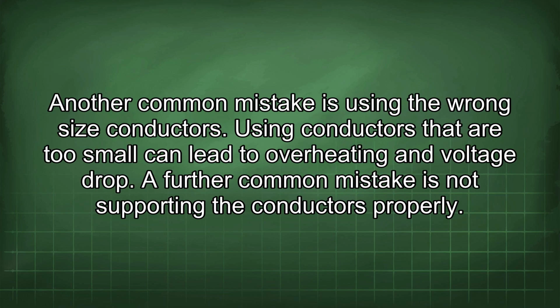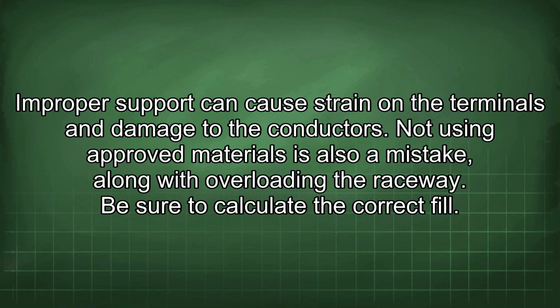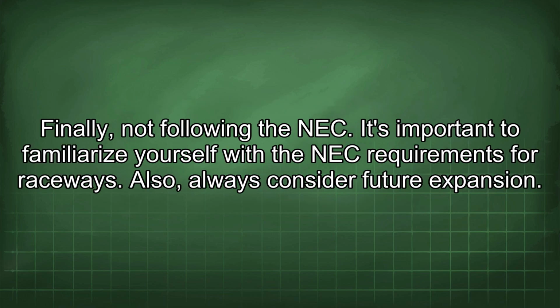Another common mistake is using the wrong size conductors. Using conductors that are too small can lead to overheating and voltage drop. A further common mistake is not supporting the conductors properly. Improper support can cause strain on the terminals and damage to the conductors. Not using approved materials is also a mistake, along with overloading the raceway. Be sure to calculate the correct fill. Finally, not following the NEC. It's important to familiarize yourself with the NEC requirements for raceways.